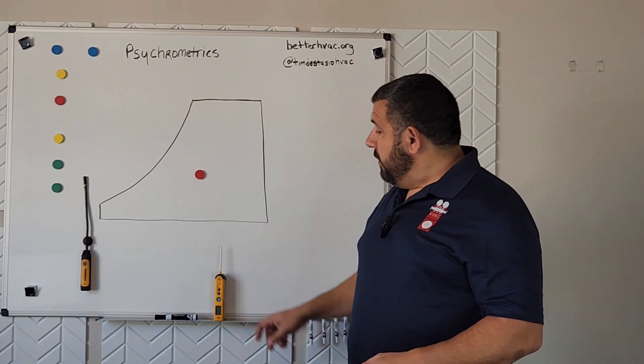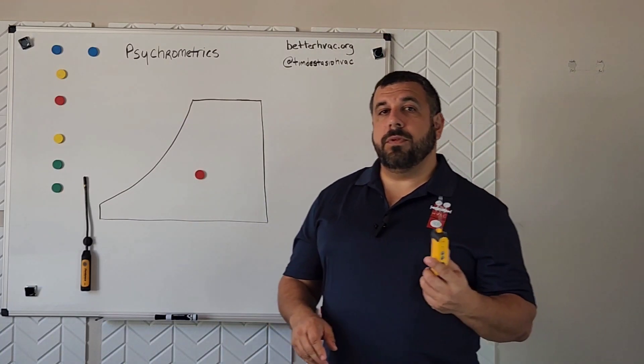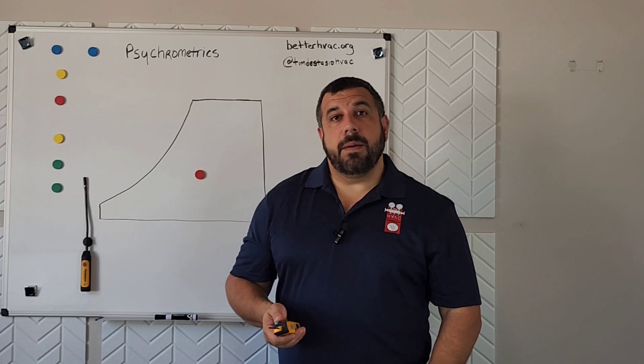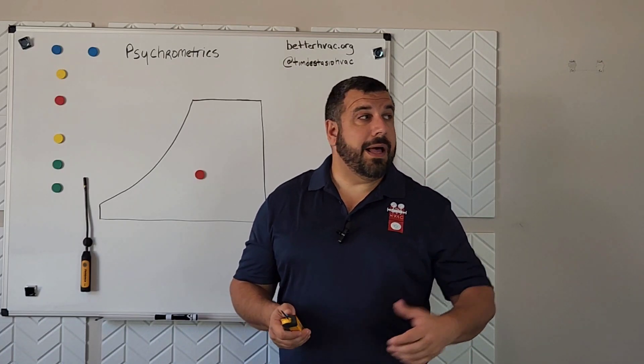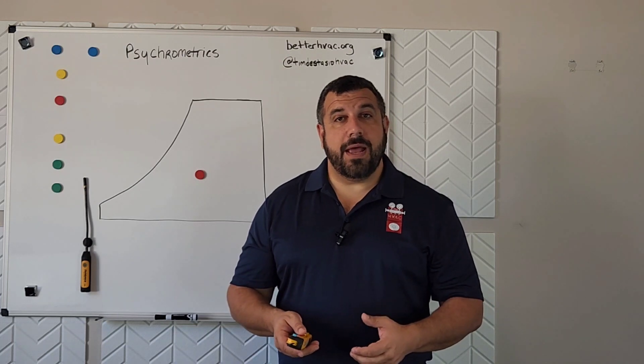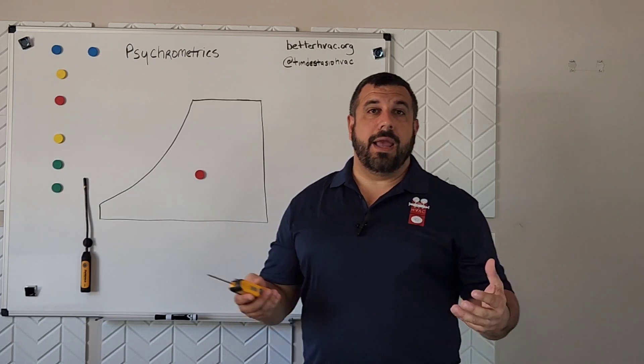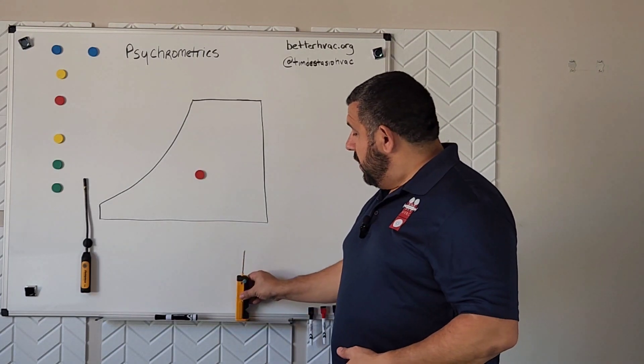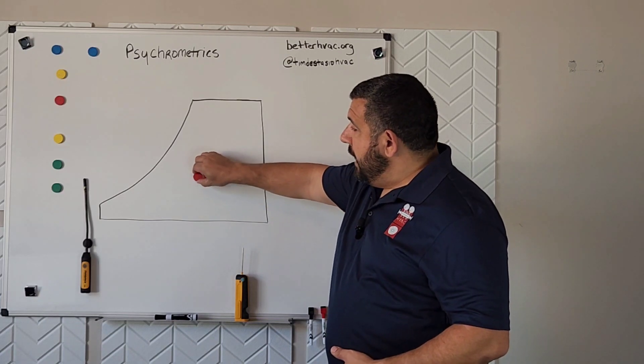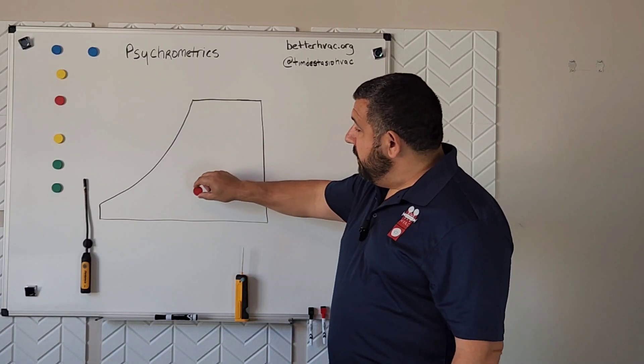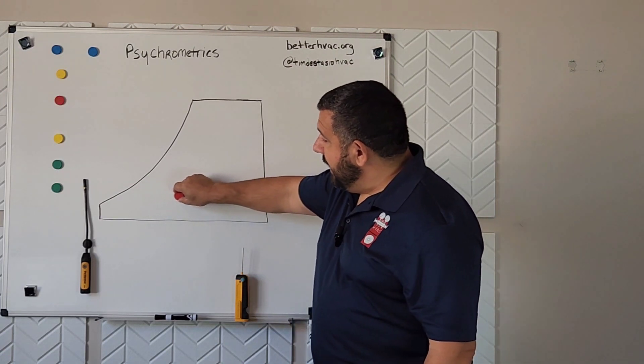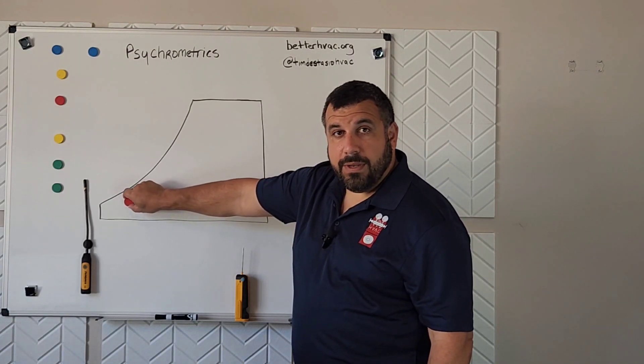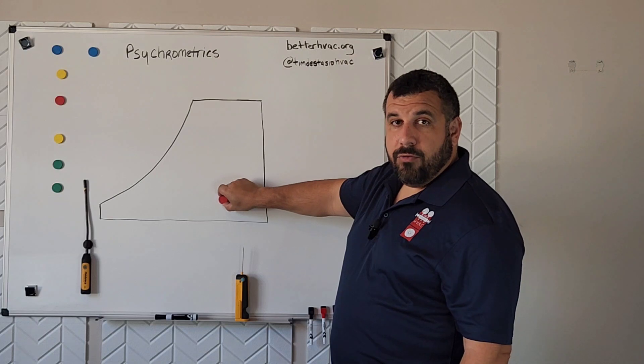When we're talking about the first property of air, which is dry bulb temperature, that's the kind of temperature that we read with a basic thermometer that you carry in your tool bag. We read the temperature rise and drop across a return and our supply. It's the same temperature that we're reading on the thermostat. Dry bulb temperature is just that — it's dry. It doesn't take into account the moisture in the air. In the psychrometric chart, when we are adding or taking away heat or dry bulb temperature from the air, we're moving our dot left and right. Left means we're taking away heat; right means we're adding dry bulb heat.